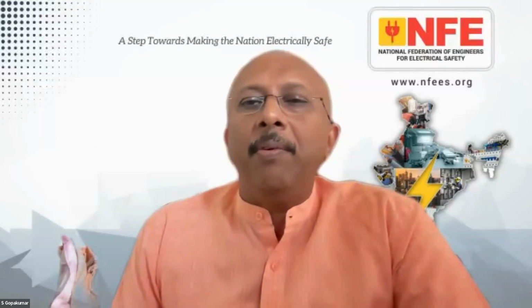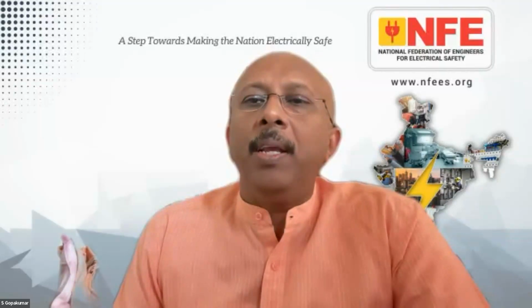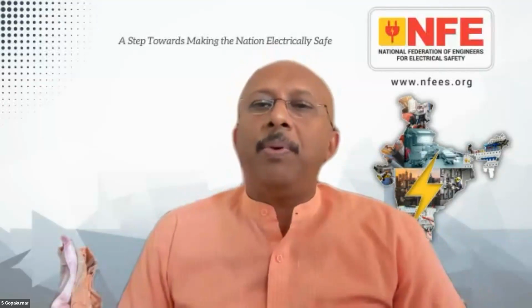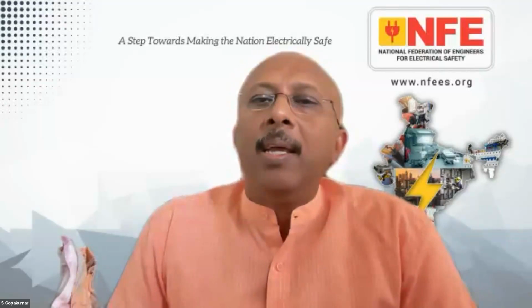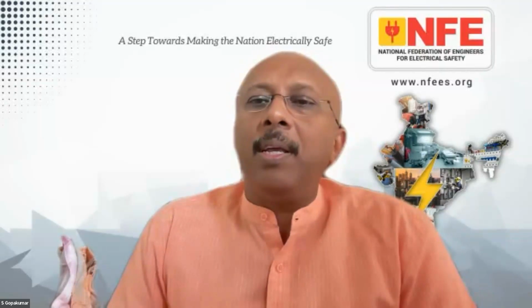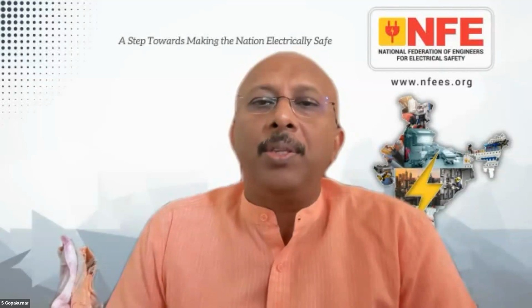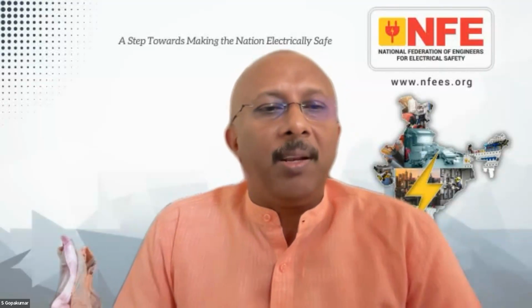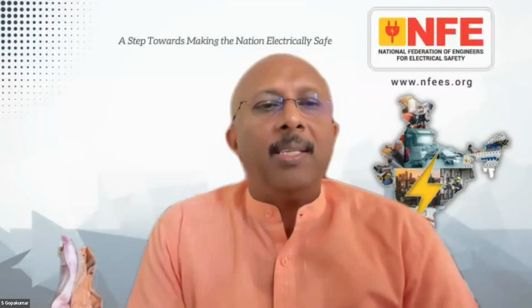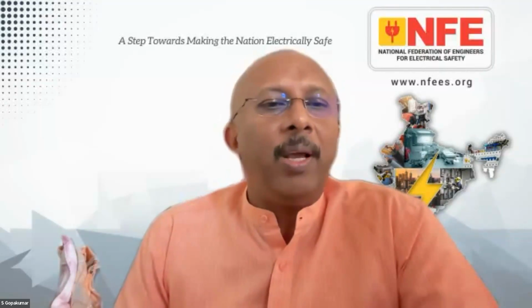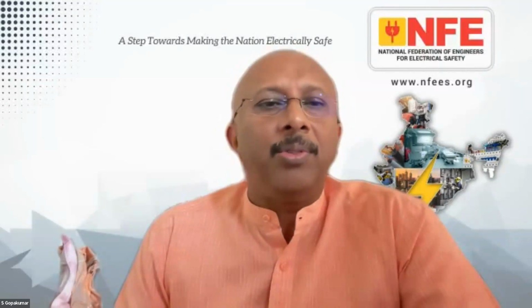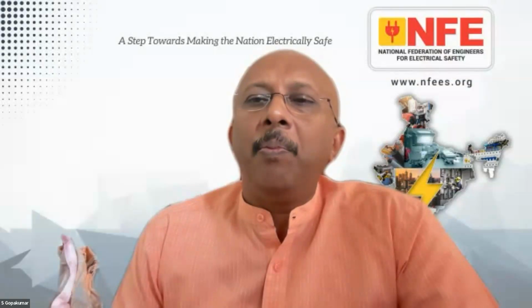Okay, thank you. So we have a question from Mr. Gajendra Patil. Can we take a lift incoming power cable and earth strip in the lift well instead of a separate shaft? Is that a correct method, please, to Vishnu sir? So he's asking whether a separate shaft is required or the cables can be taken through the same shaft. The earth, he means the earth strip, right? Earth strip can be taken from the existing elevator shaft, both power cable and earth strip.